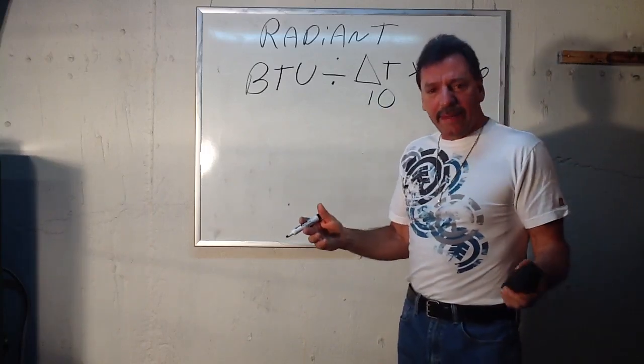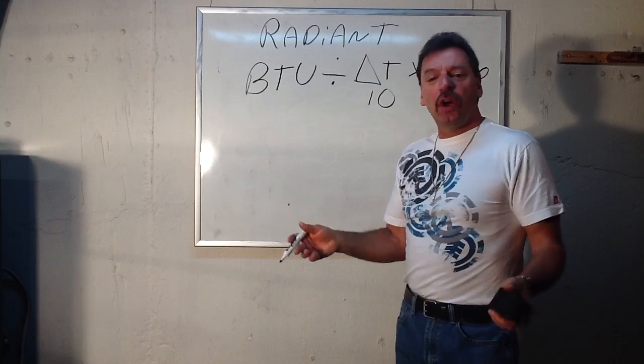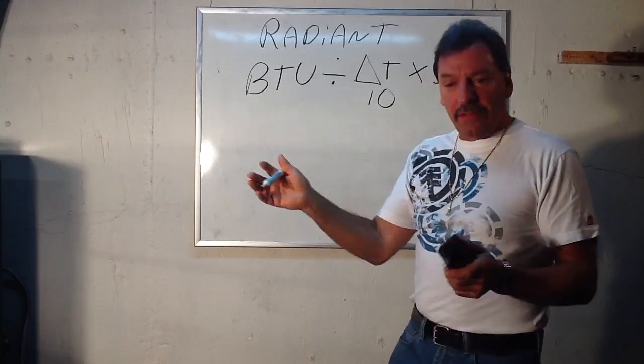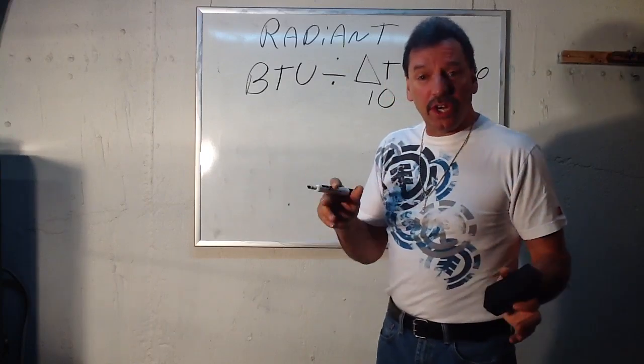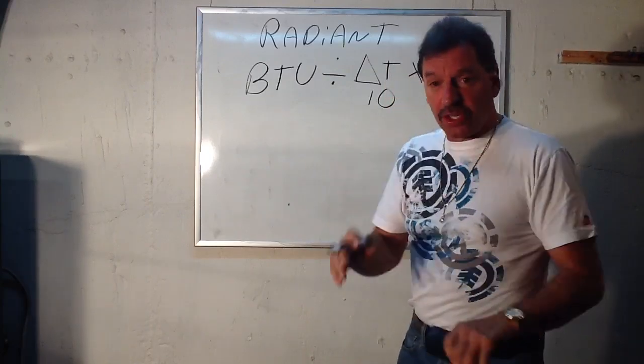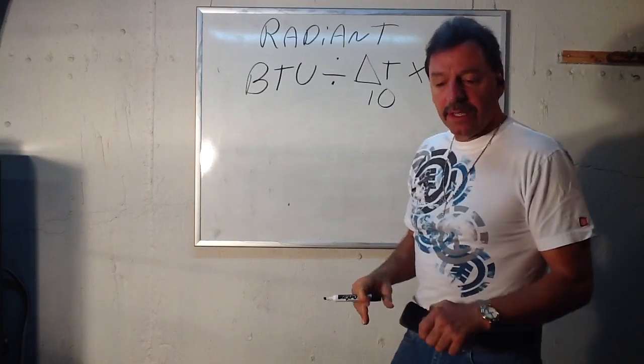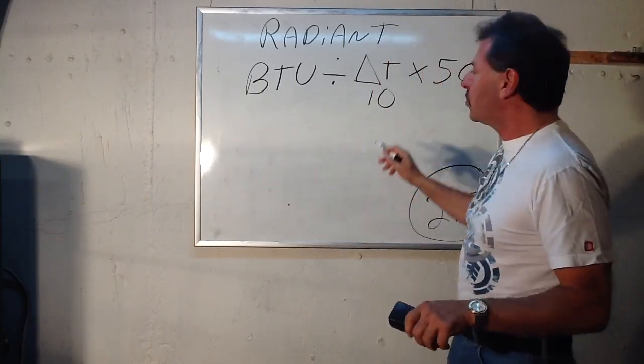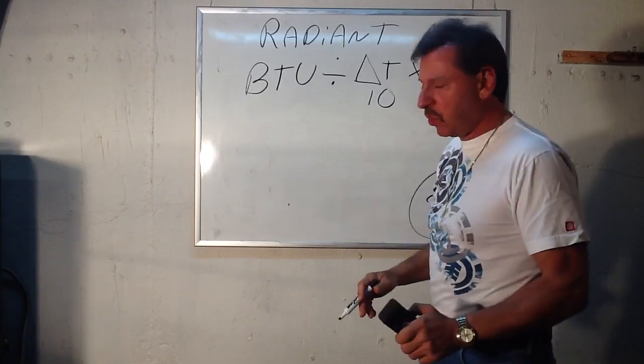Normally on baseboard it's 20, on radiant heat it's normally 10. If you use a different number because you raise the radiant heat higher, you got a fast moving circulator, whatever that water is returning at, there is going to be a difference because it's going to cool. That's the number you would use. Okay, so the Delta T is the difference: with radiant heat it's usually 10, baseboard it's usually 20.